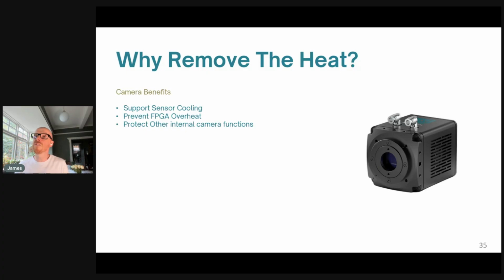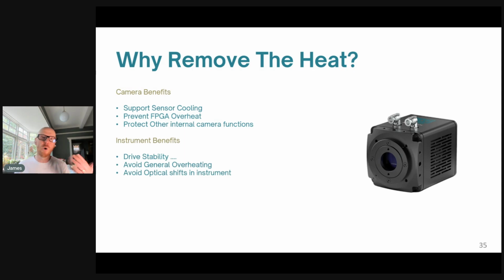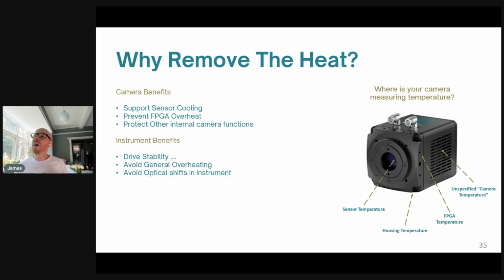So there are benefits to the camera, and also benefits to stability. You want to drive stability in your instrument, avoid general overheating, avoid optical shift - avoid your equipment heating up or things moving because you've got a heat-generating source inside your instrument. But where are you actually making these measurements?